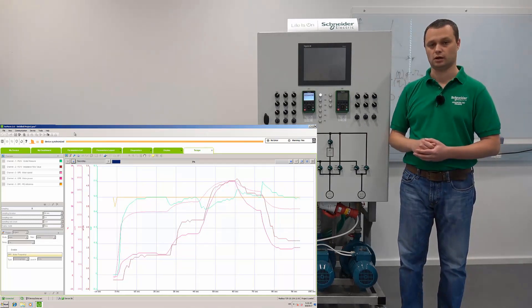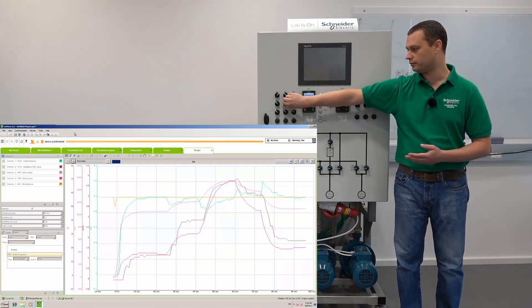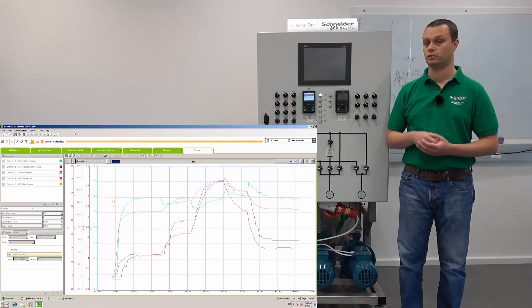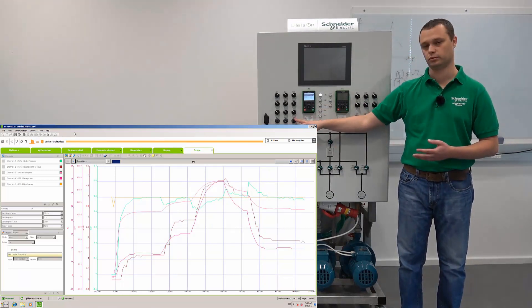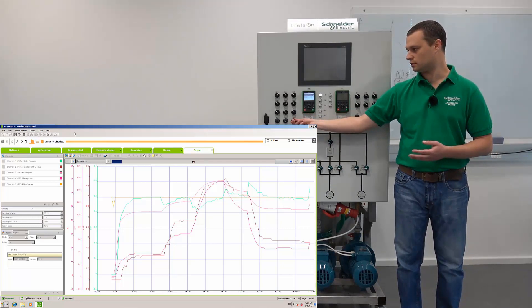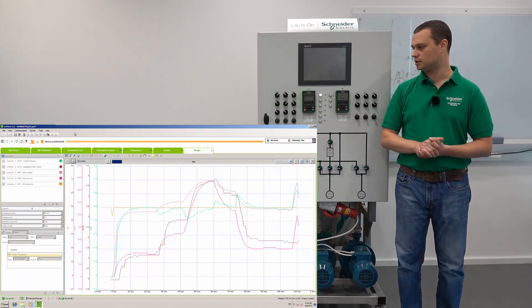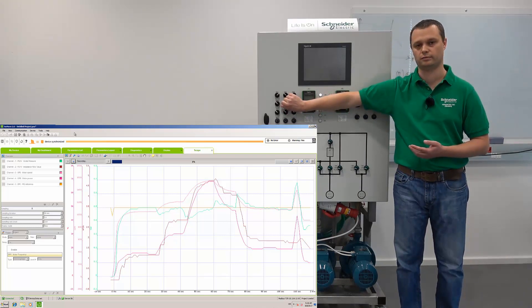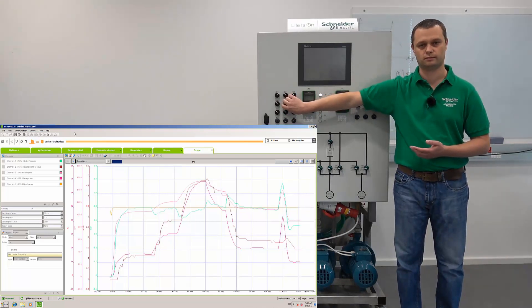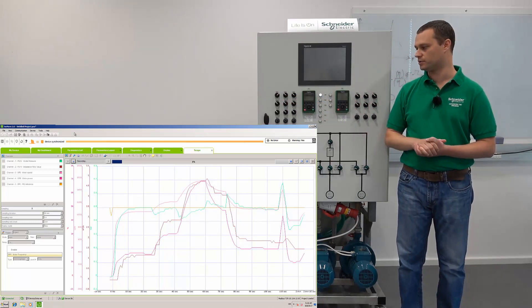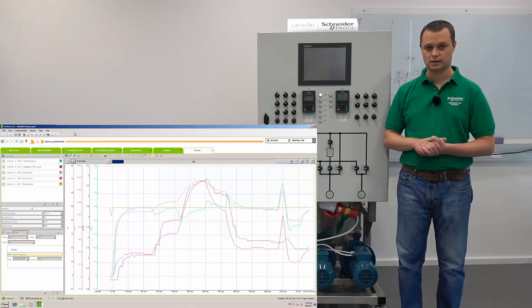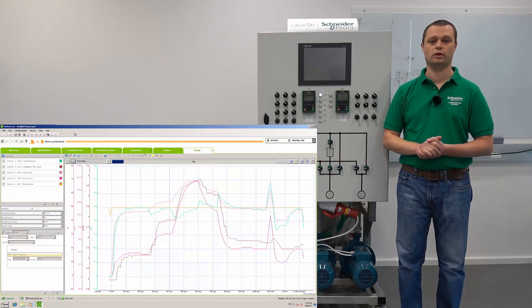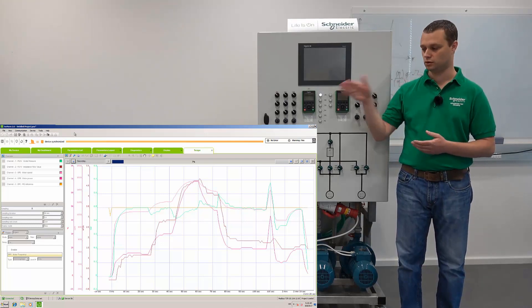Now let's check manual mode — with logical input 5 we switch to manual. The drive is no longer following the PID speed setpoint but is following analog input 3. If we increase the potentiometer, speed increases; if we decrease, speed decreases — we are in manual mode. As soon as we switch digital input 5 back, the PID takes over and we see it ramp up to follow the pressure. We can now stop the drive and do a more thorough analysis of the scope trace.